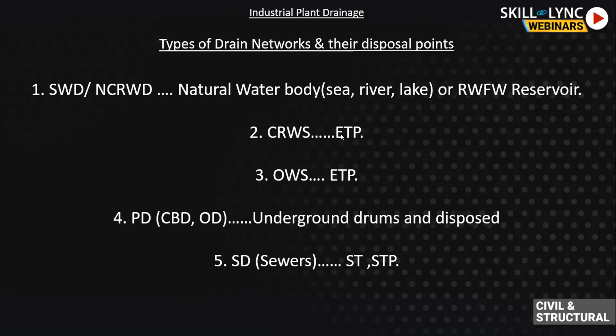Coming to the contaminated rainwater sewer or firewater sewer, they are not open. It is contaminated. Some contamination is there. So it is water mixed with contaminants, but still, if something falls in it, even a human foot falls in it, it can have some hazard. So this CRWS is always a closed conduit system. We have learned in hydraulics open channel flow. So SWD is open channel flow. CRWS is closed conduit system, closed pipe flow. And CRWS material of construction is generally carbon steel pipes or RCC pipes. You must have seen RCC pipes on the sides of the road, our municipal roads, when some construction is going on, huge RCC pipes are there. So they can be used for CRWS type of system.